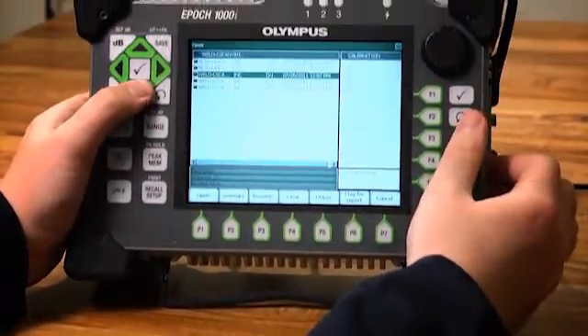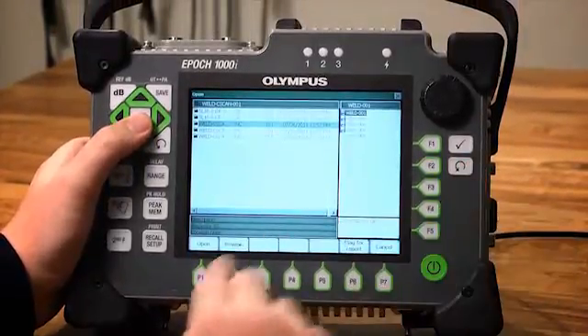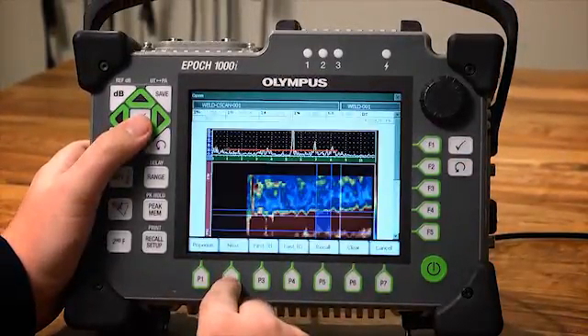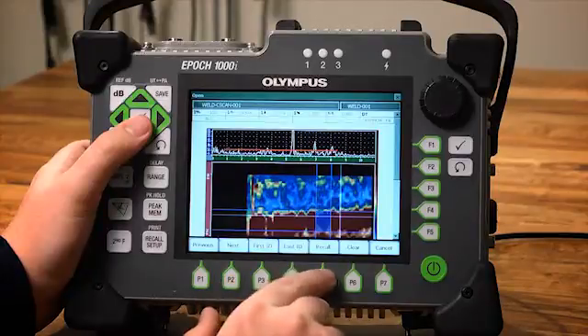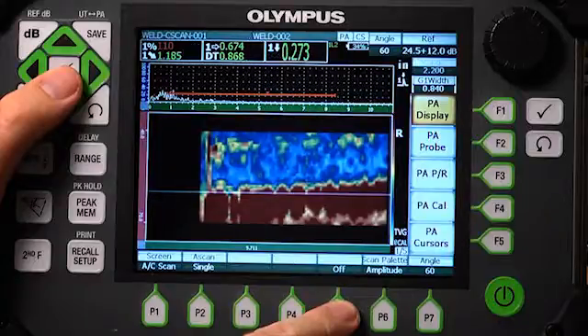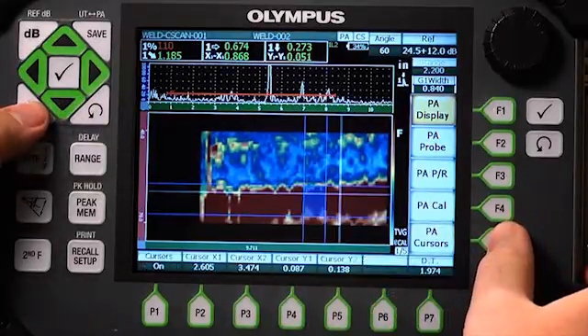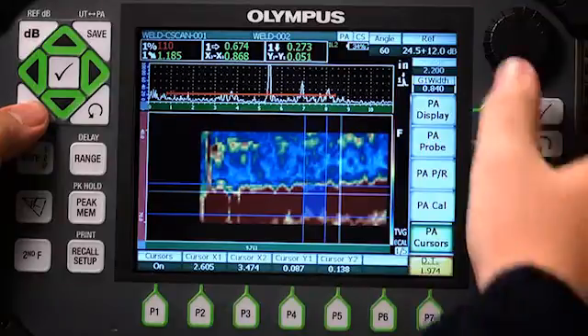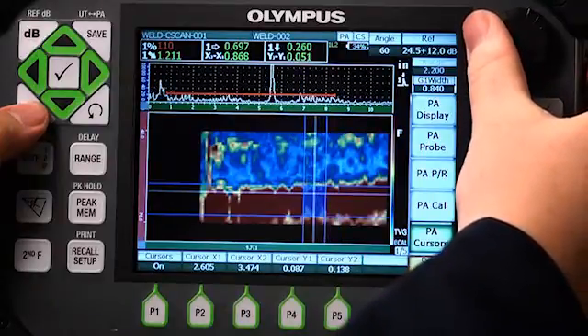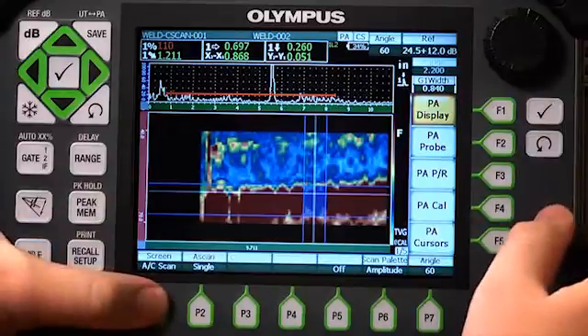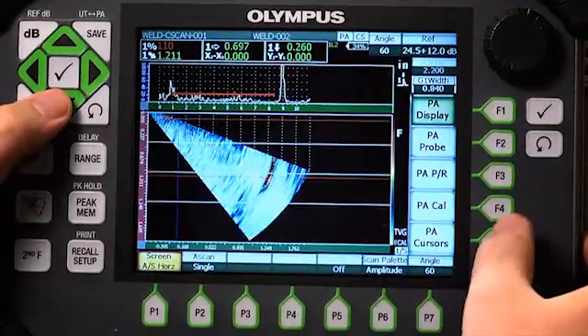Once you have completed a C-SCAN, it can be stored in the EPOCH 1000i datalogger. Along with the C-SCAN, compressed A-scans for each C-SCAN point are also stored for basic visual analysis after the scan is completed. These compressed A-scans can be used to recreate the sector or linear scan from a selected slice of the C-SCAN for enhanced image review. The EPOCH 1000i encoded C-SCAN option contains powerful imaging capabilities to enhance inspections for faster and easier interpretation and reporting.